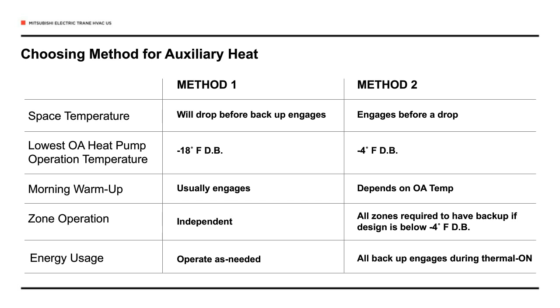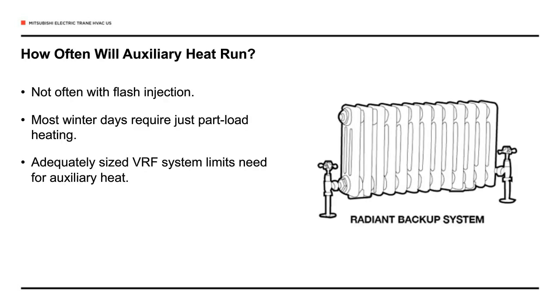How often will the auxiliary heat run? If you're using flash injection technology, probably not much, if at all. Matter of fact, we see very few designs where people are using the flash injection product and also putting in auxiliary or backup heat systems. Most winter days only require part load heating. We'll see that here on the next screen.